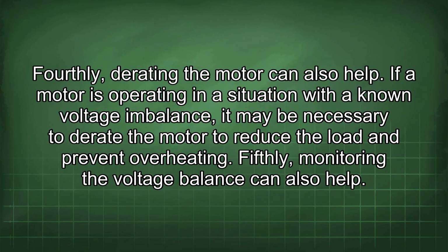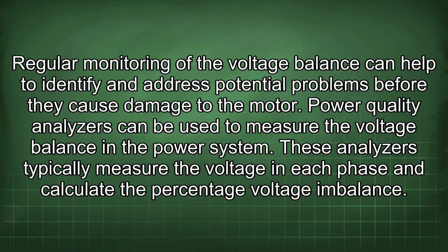Fourthly, derating the motor can also help. If a motor is operating in a situation with a known voltage imbalance, it may be necessary to derate the motor to reduce the load and prevent overheating. Fifthly, monitoring the voltage balance can also help. Regular monitoring of the voltage balance can help to identify and address potential problems before they cause damage to the motor. Power quality analyzers can be used to measure the voltage balance in the power system. These analyzers typically measure the voltage in each phase and calculate the percentage voltage imbalance.